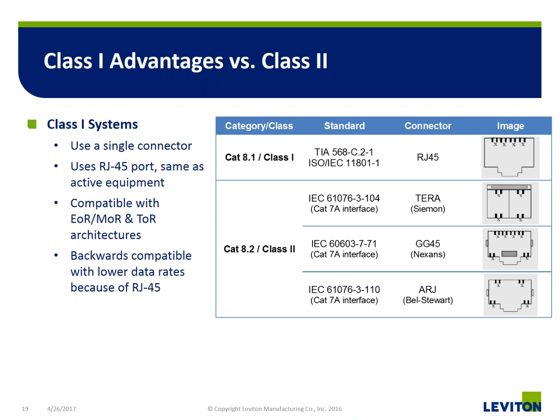And by that I mean, with a top of rack architecture, you're using essentially a patch cord that's going to connect the switch directly to the server. If both of those active pieces of equipment are using an RJ45, that by definition eliminates a Class 2 patch cord from being able to be used. And then you've also got the ability of backwards compatibility with the lower data rates because of the RJ45.